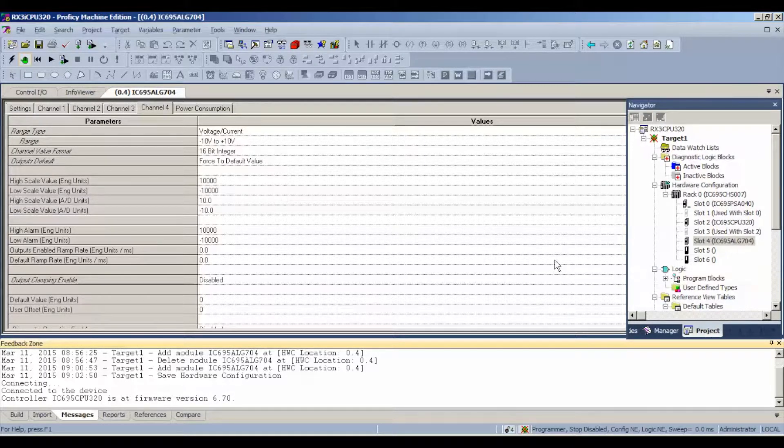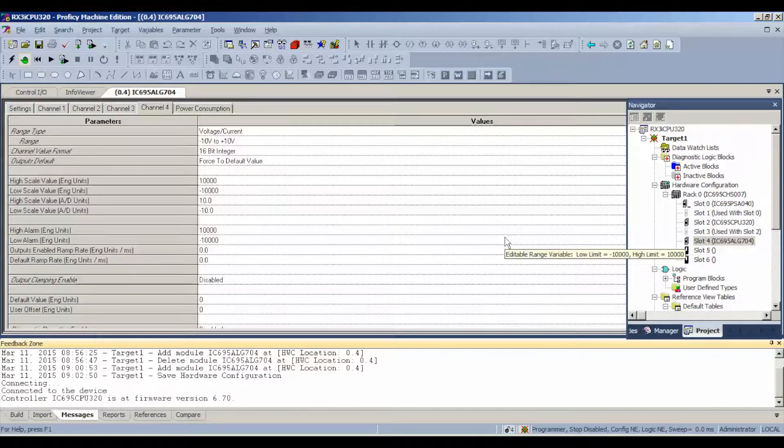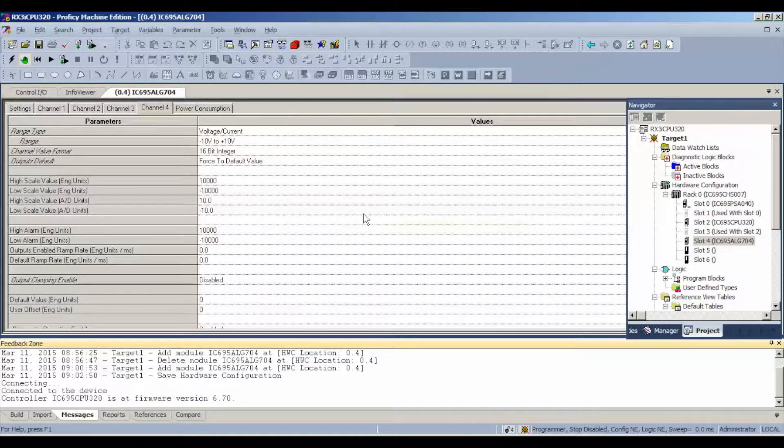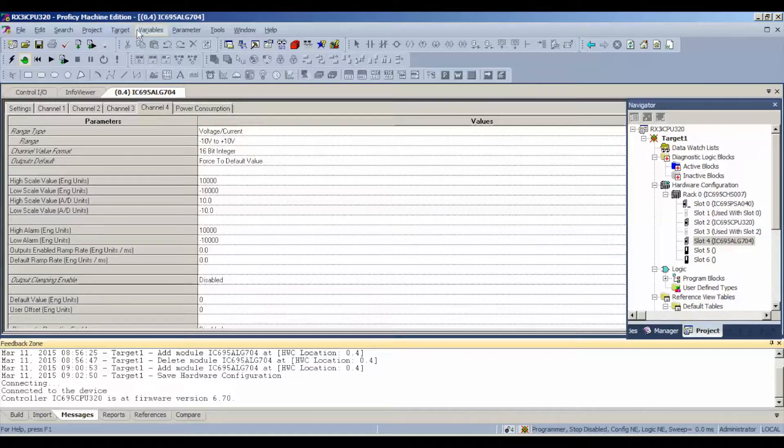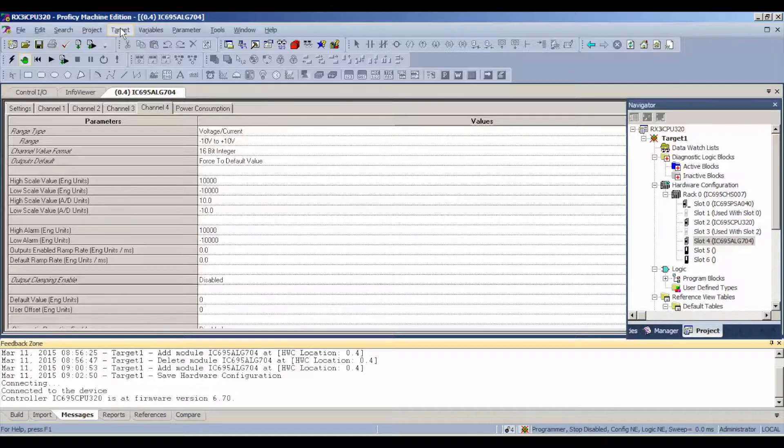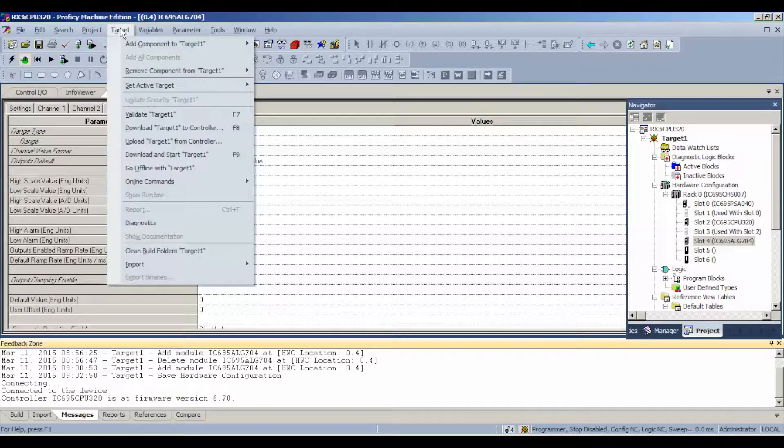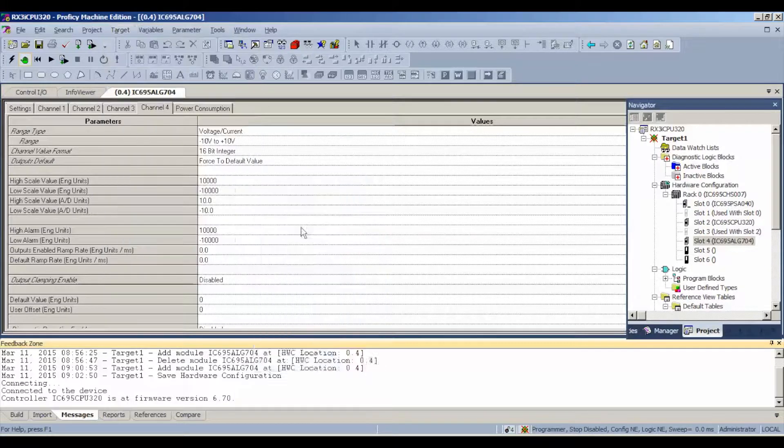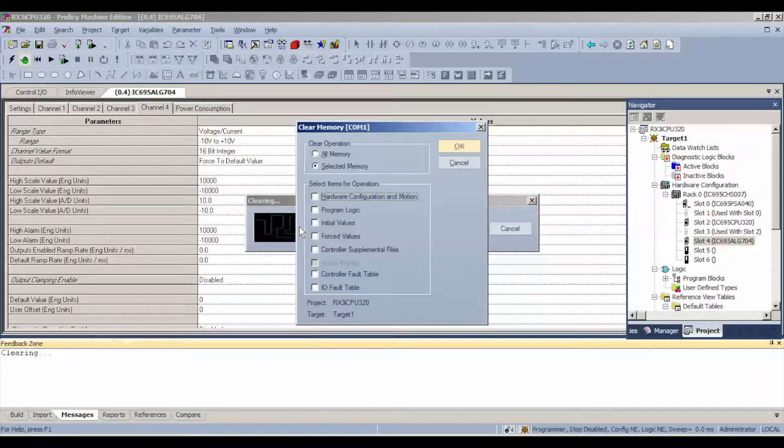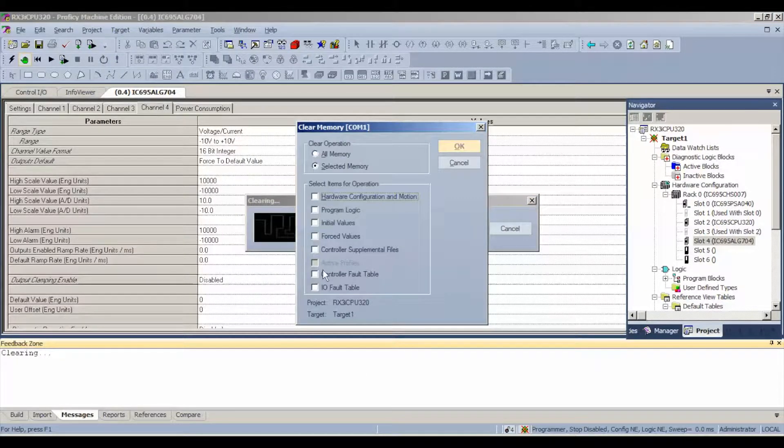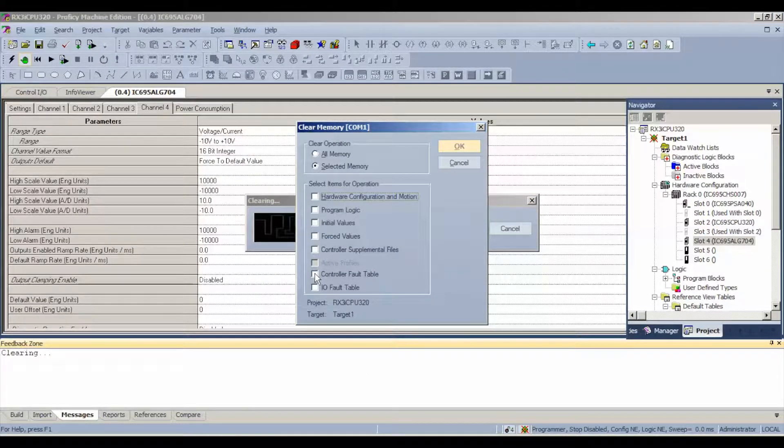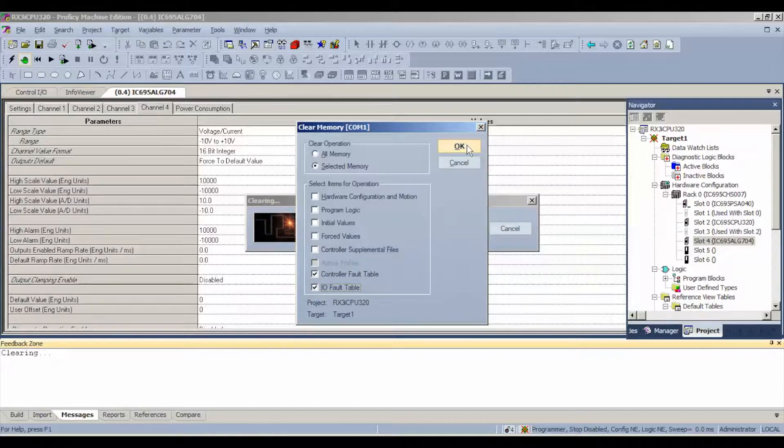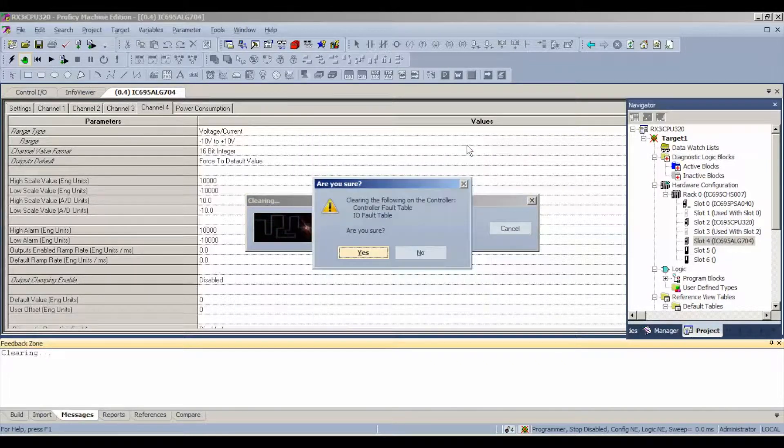It's technically faulted. What we do here is go to target, online commands, clear, and we only want to clear those faults that we've created, controller fault table and I.O. fault table, and hit okay. You're going to get hung up if you don't do this before you download, so make sure that you've done that.